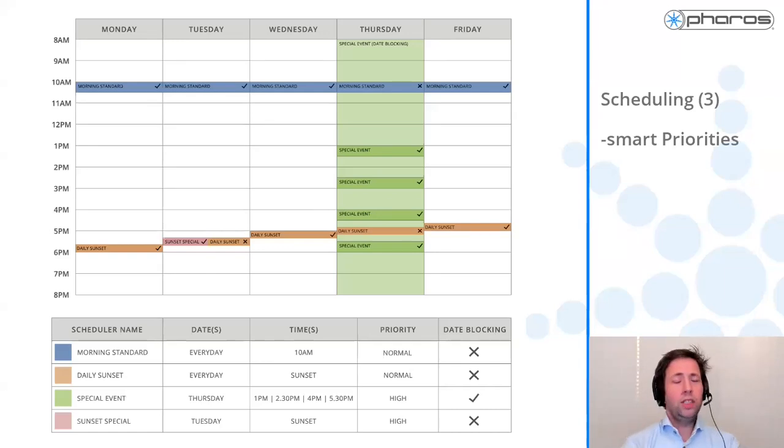Now, let me first go to a request. The customer comes in, or yourself, you figure out, but this Tuesday it should be doing something different. Now, I don't need to go in and start changing the daily sunset trigger. I can just program a new daily special trigger, but I set that to a higher priority. At Tuesday sunset, both the daily sunset and the sunset special are scheduled, but because the sunset special has a higher priority, only that schedule will fire. And we are showing here the little tick marks and crosses. This will also be shown in the online scheduler itself to show which trigger will fire.